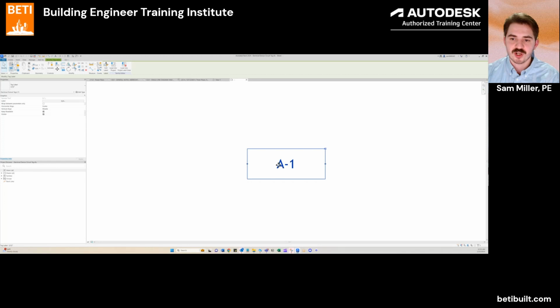So it shows A-1 - this becomes a matter of preference. I like it to read panel name dash circuit, so I write a suffix of a dash and apply. It's getting better, but there's still a gap, which I'd like to get rid of. I hit the down arrow on the spaces column, make it 0, hit OK, and now it's a clean panel dash circuit number with no spaces.